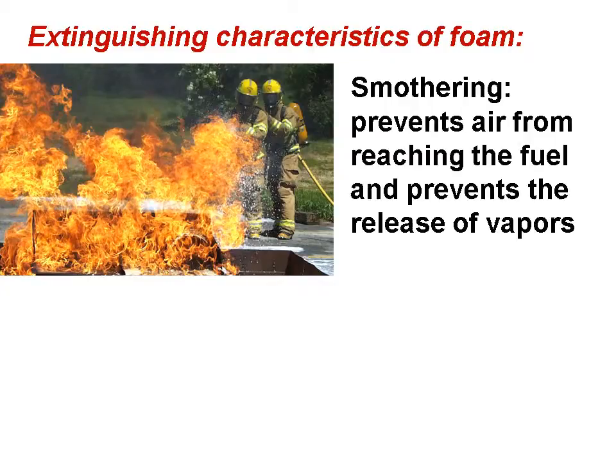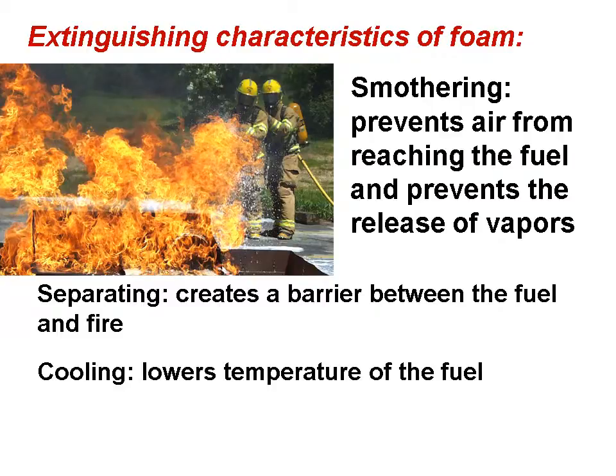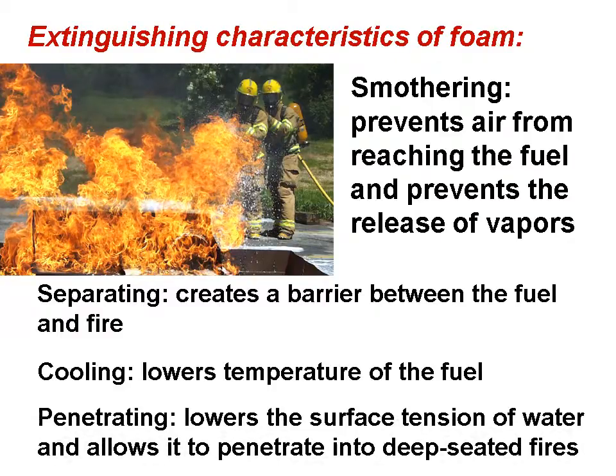The extinguishing characteristics of foam: the smothering prevents air from reaching the fuel and prevents the release of vapors. The separating creates a barrier between the fuel and the fire. It lowers the temperature of the fuel, and it lowers the surface tension of water and allows it to penetrate into deep-seated fires.